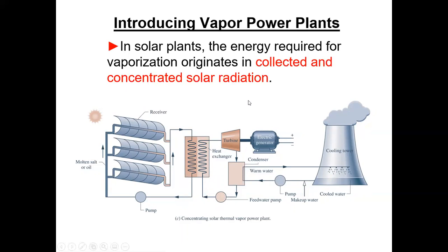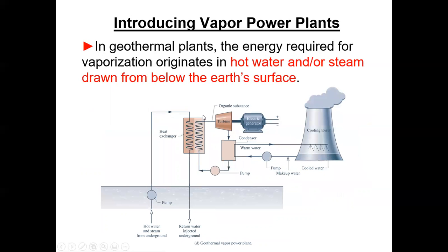Now, temperatures and pressures do change based on energy stored. And I know in most nuclear plants, the turbine rotation speed is 1,800 RPM. Coal plants, it's 3,600 RPM. So down to the nitty-gritty detail of the actual components, there are some differences. But in theory, the Rankine cycle just needs heat input to make it go. And this is geothermal.